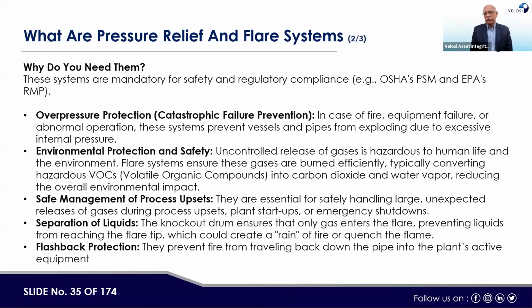So why do we need them? First of all, as we said, there are nine layers of protection in general. The relief system is one of the basic protective systems, where overpressure protection can be managed by the PSVs. If the PSV does not protect, then there could be an explosion, leakage or rupture, which can affect the equipment as well as the people, safety and environment. Then there is management of process upsets, separation of liquid, and flashback protection, which is also part of why we need these flare systems.